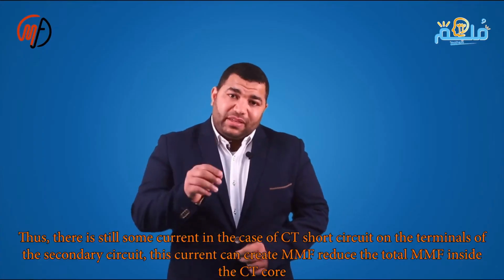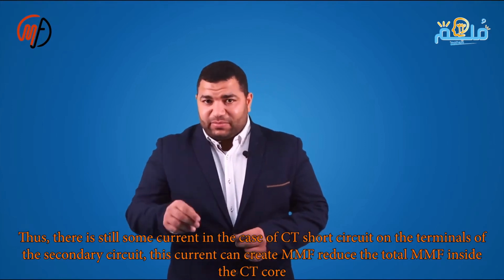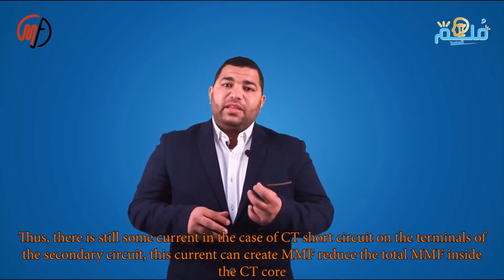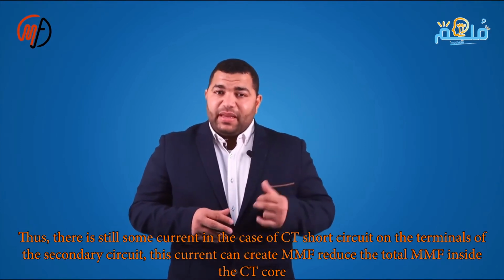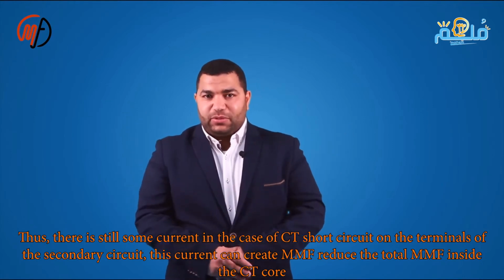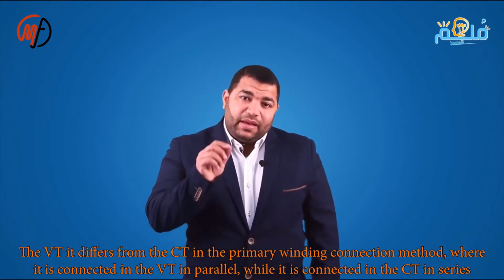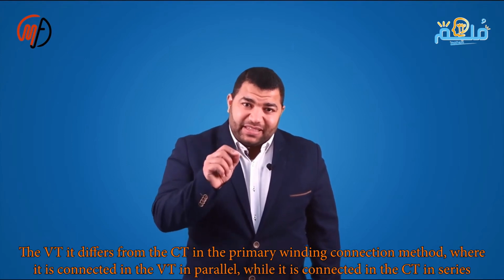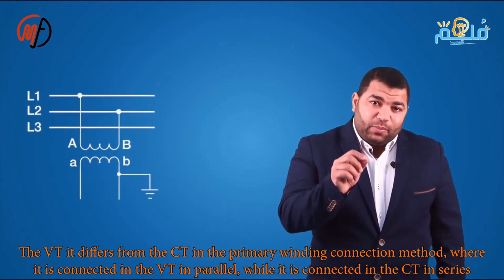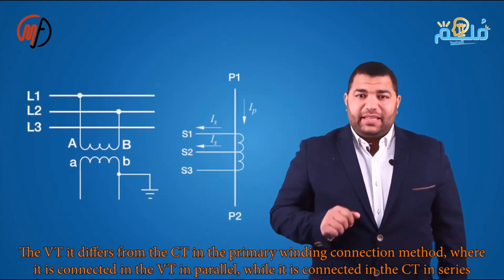Current in the short circuit prevents CT secondary voltage rise. VT is parallel, CT is series. Primary CT current is constant. Primary VT current depends on the secondary load. Secondary load generates primary current. Without it, both disappear. MCBs or fuses protect the VT secondary from short circuits or high currents. Opening the CT secondary or shorting the VT secondary is dangerous.